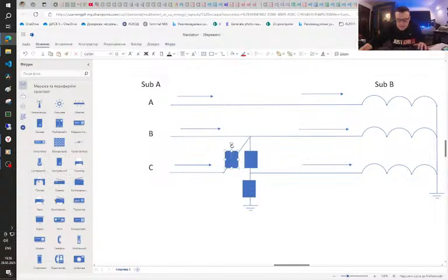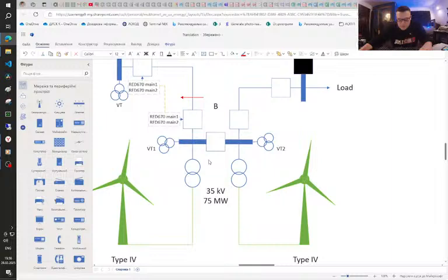and in this particular case it looks like this arc impedance was bigger than the impedance of this little part of line, and also the zero sequence impedance of the transformers, because here we have two 40 megawatt transformers with grounded neutral, and they work in parallel.